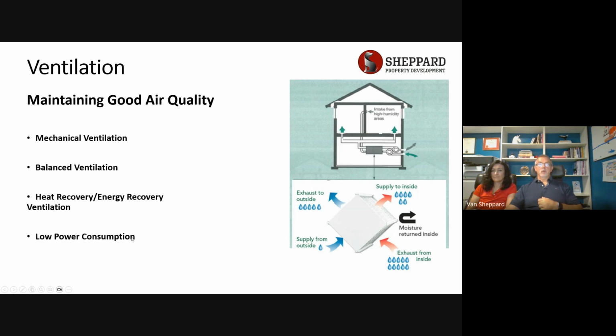And as I say, it's a low power consumption unit because the fans are small and the flow rates are quite low, and they're high efficiency. So I think the units that we spec for our latest project are ERVs, and I think they're 77% efficient. So they pull a lot of heat. Either they pull it out or they return it, depending on whether you're in heating or cooling mode, passively, so you don't have to use your heating system to make up that heat loss.